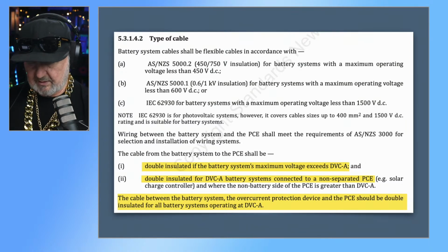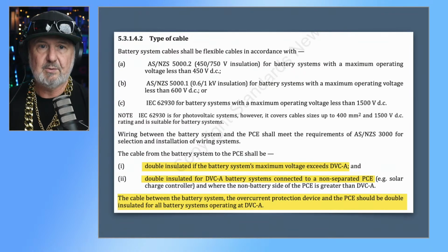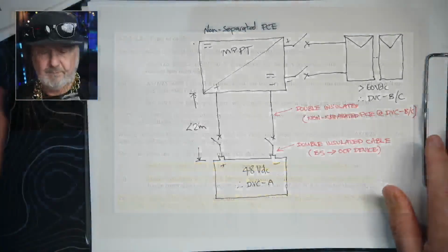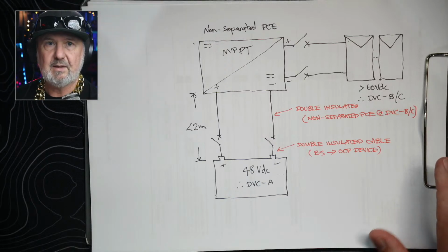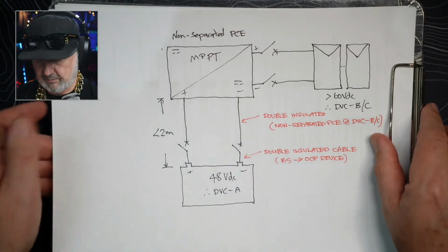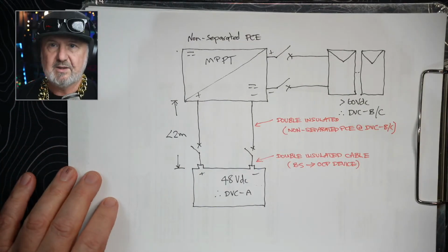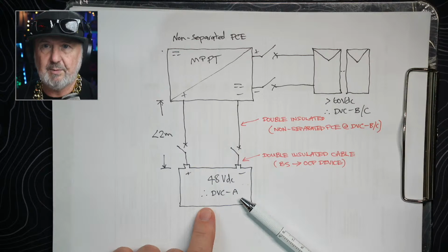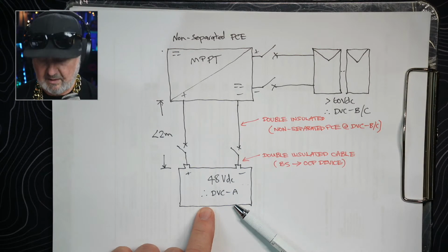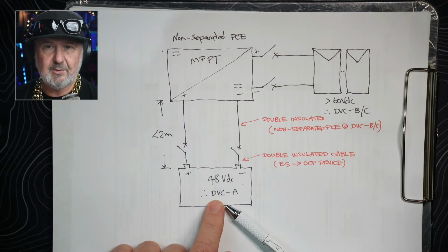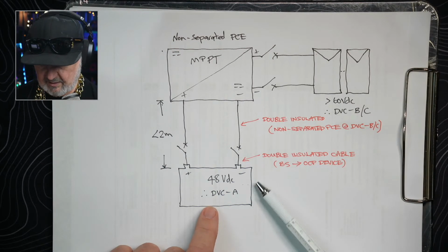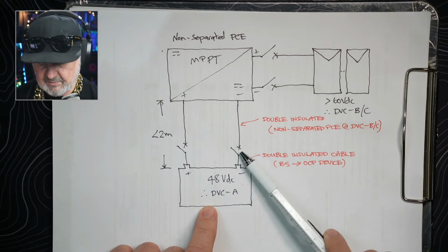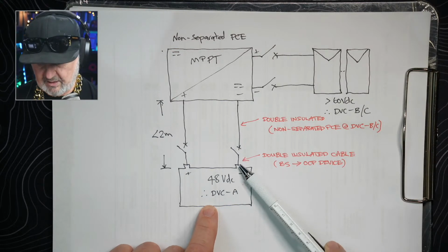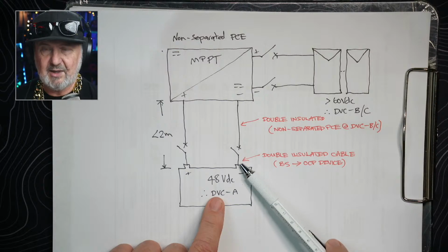Now, I think I've got a little drawing of this. Where's my drawing? Okay, here's my little drawing. So bring it out there a little bit. So let's say we have a 48-volt battery system, and it's DVC-A, so it's a lithium-ion battery. It doesn't get over 60 volts. We need double insulated cables between the battery system and the overcurrent protection device. So even though it's DVC-A, we still need double insulated cables at that point.